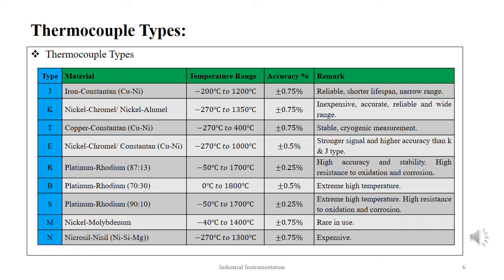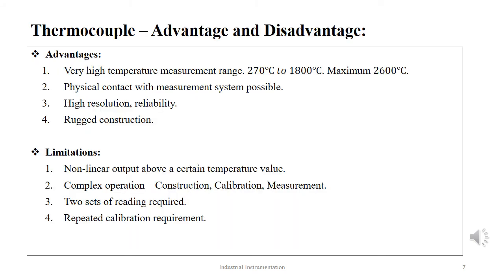J, K, T, and E type thermocouples are called base metal thermocouples, which are the most common type of thermocouples. S, R, and B type thermocouples are called the noble metal thermocouples, which are used in high temperature measurement applications. The advantages of the thermocouple are that they are capable of measuring temperature directly up to 1800 degrees Celsius. Very few special thermometers can measure up to 2600 degrees Celsius. The devices can be brought in contact with the system under measurement. The thermocouples have very high resolution and reliability of measurement. The thermocouples are rugged and robust in build.